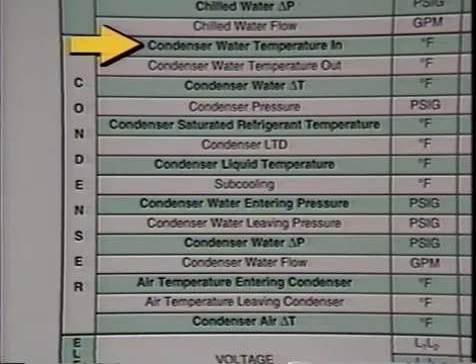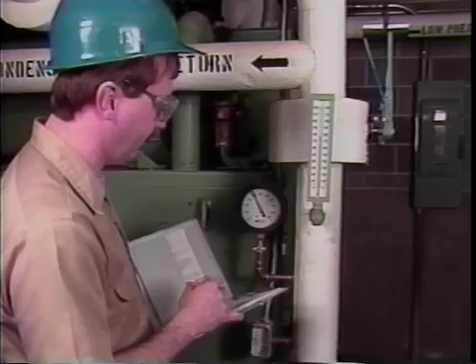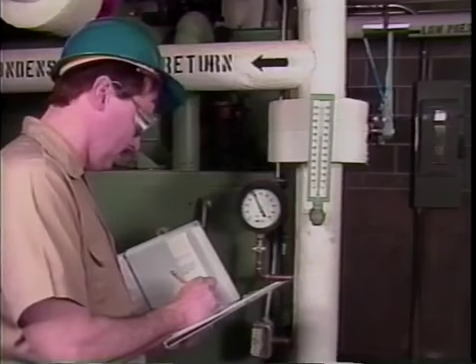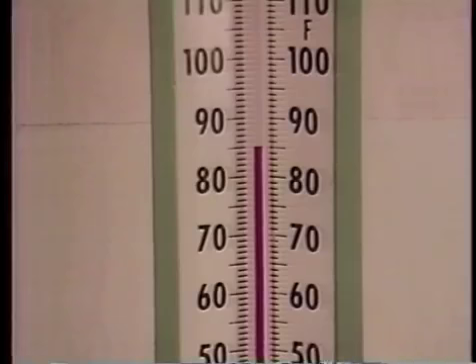Water temperature entering the condenser. This temperature should not exceed the design entering water temperature and on most installations should not drop below 70 degrees Fahrenheit. Entering condenser water temperature can be up to 95 degrees. However, 85 degrees is more typical. If the entering water temperature drops too low, the condenser head pressure will not be high enough to supply refrigerant through the expansion valve.